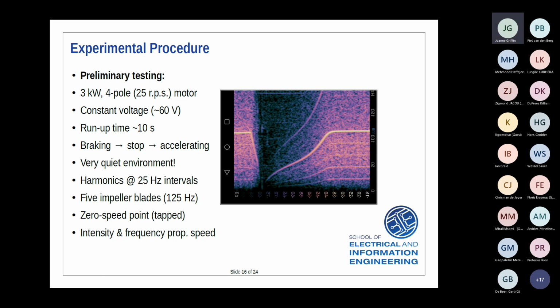Once again, I just want to reiterate, because there are 5 impeller blades, there's a relation of 5 times the machine speed. So we're going to get harmonics at 25 hertz spacings: 25, 50, 100, 125 hertz. And you can see the fifth harmonic is the clearest out of all of the others. So the clearest audio waveform. And that basically represents our speed versus time trace very clearly.